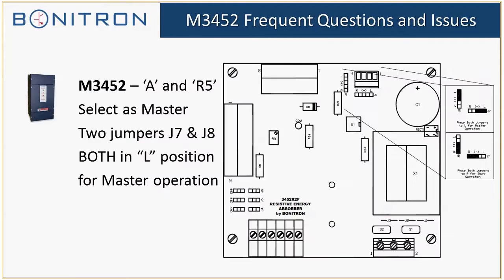So, moving on to specific questions and specific issues. This is our 3452. It's our most common braking transistor, braking chopper. It functions as a shunt for the VFD to place energy into a resistor and burn it up as heat, rather than have a drive fault out on overvoltage.